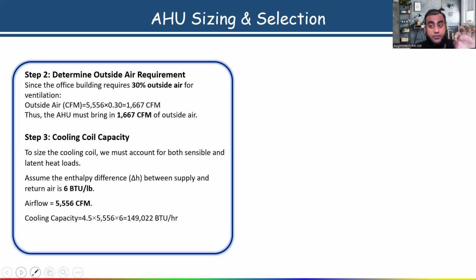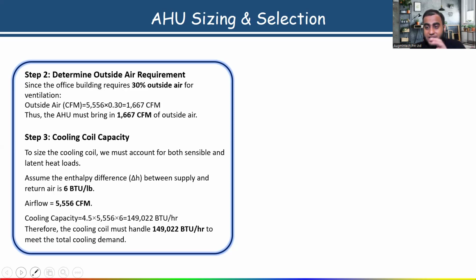So this detail we have to submit to the manufacturer. Okay, remember: first, airflow in CFM; second, outdoor air requirement; third, cooling coil capacity. These are the details which we have to submit to the manufacturer for the selection of AHU. As per that, they will give you the model numbers, supply air outlet size, return air outlet size. That I will explain to you, from where actually.